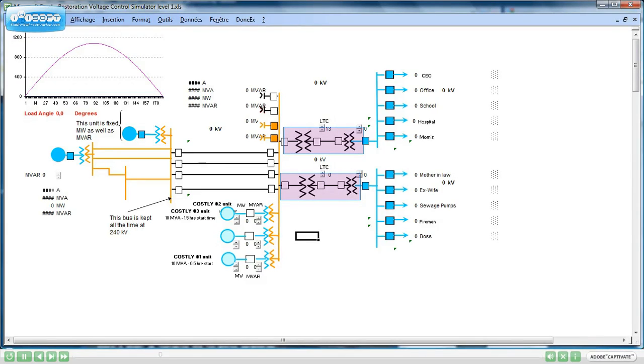There are 2 radial sets of transformers. The top and bottom ones are 240 to 138 kV transformers. In series there are 138 to 25 kV transformers. All transformers are equipped with load tap changers that can be adjusted with wheels. Then there are distribution buses with feeders.